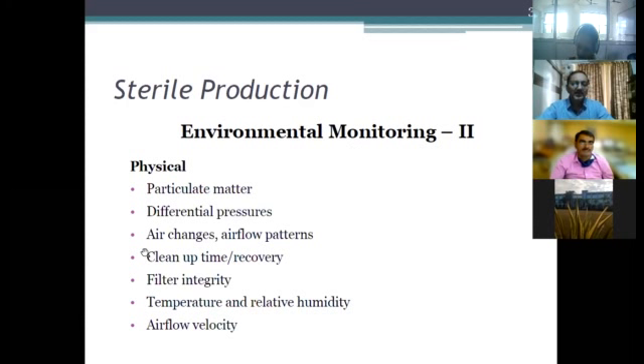So air changes are very important. There's a regulation which says that if you have a class 10,000 area, the air changes should be not less than 20 to 30 air changes per hour, which means the whole air in the room has to be changed 30 times in 1 hour. So you need to design an AHU for this purpose. We'll come to the design of the AHU also, and you will be able to understand.